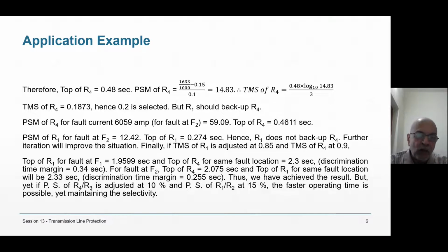Now the PSM of R4 is 6059 for another fault. So for that, the PSM is 59.09. I cannot take that, I have to take 20. So the top of R4 is 0.4611. TMS 0.1 I cannot take, hence 0.2 is selected. 0.2 I cannot change. And PSM of R1 is 12.42. Top is 0.274. So R1 operates earlier than R4.